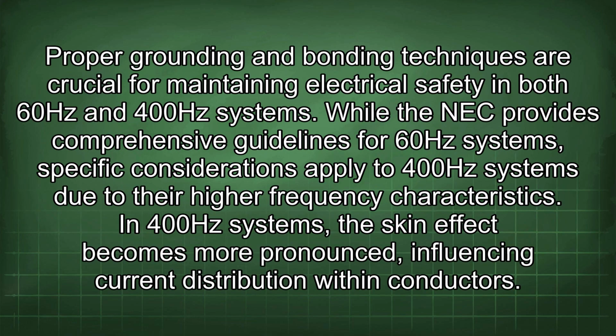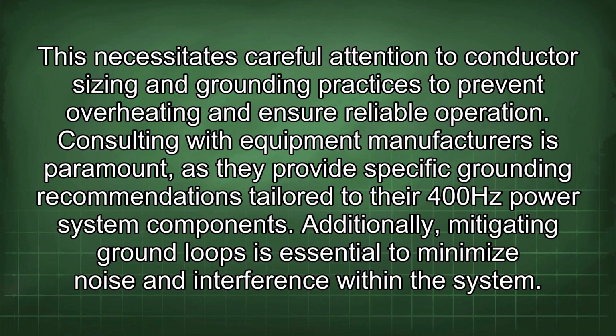Proper grounding and bonding techniques are crucial for maintaining electrical safety in both 60 Hz and 400 Hz systems. While the NEC provides comprehensive guidelines for 60 Hz systems, specific considerations apply to 400 Hz systems due to the higher frequency characteristics. In 400 Hz systems, the skin effect becomes more pronounced, influencing current distribution within conductors. This necessitates careful attention to conductor sizing and grounding practices to prevent overheating and ensure reliable operation.